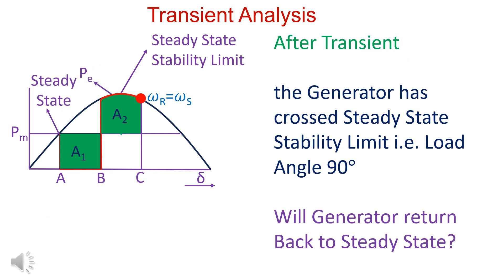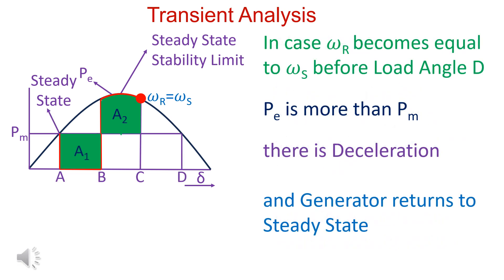In the case considered, load angle has crossed steady state stability limit, that is load angle 90 degrees. Question is whether generator returns back to steady state or not. In case Omega R becomes equal to Omega S before load angle reaches D, PE is more than PM. There is deceleration and generator returns to steady state.